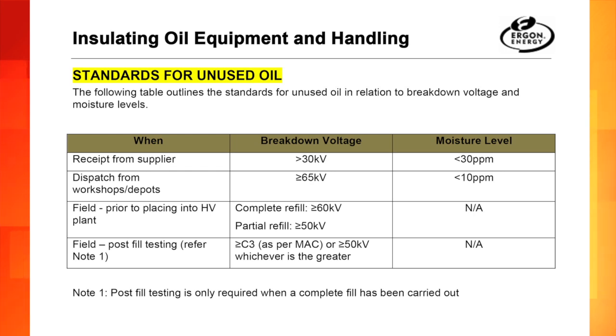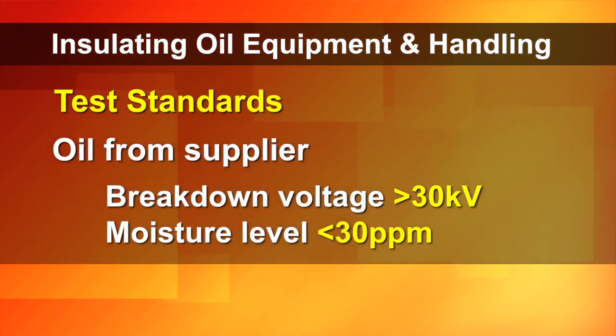Okay, just a little bit on the test standards. It varies through the life cycle of the oil as it goes from the supplier right through to when it goes into HV plant. When we get oil from the supplier, we're requiring at this point in time that oil have a breakdown voltage of greater than 30 kV and less than 30 parts per million. This may change in the near future as we are currently negotiating a new oil contract. So as I say, those criteria may change.